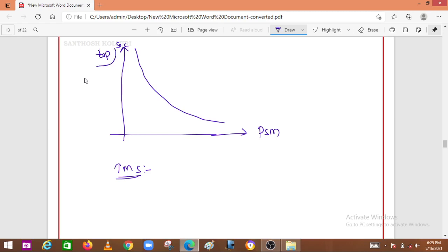So operating time and time multiplier setting have a relation like this: TMS in terms of percentage divided by 100, into T operating time when the relay has 100% time multiplier setting. Based on that, you can change the operating time of the relay.